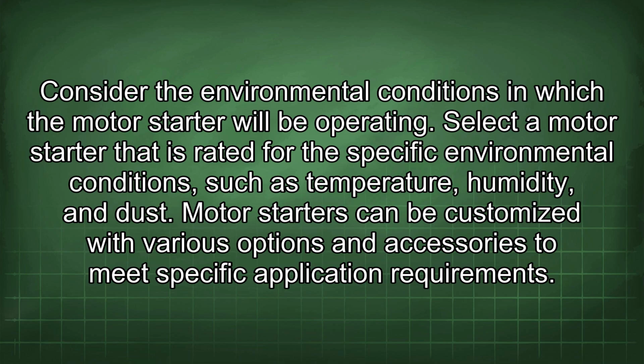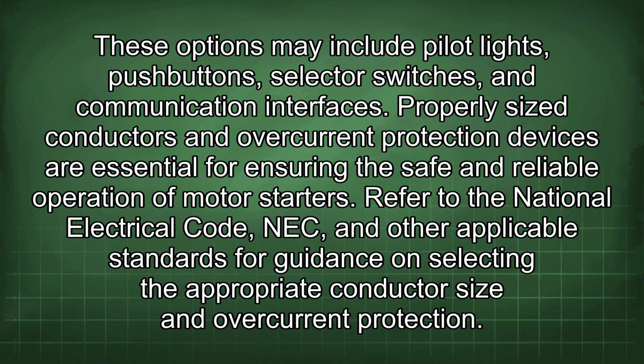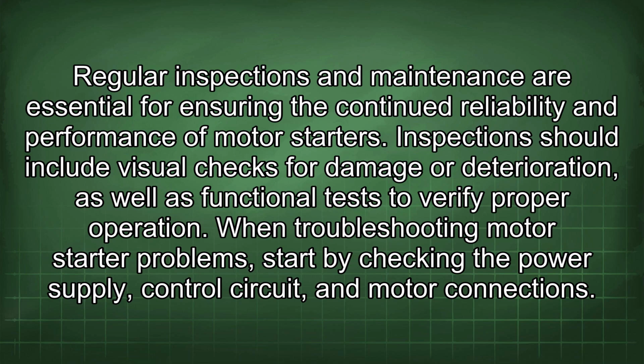Consider the environmental conditions in which the motor starter will be operating. Select a motor starter that is rated for the specific environmental conditions, such as temperature, humidity, and dust. Motor starters can be customized with various options and accessories to meet specific application requirements. These options may include pilot lights, push buttons, selector switches, and communication interfaces. Properly sized conductors and overcurrent protection devices are essential for ensuring the safe and reliable operation of motor starters. Refer to the National Electrical Code, NEC, and other applicable standards for guidance on selecting the appropriate conductor size and overcurrent protection. Regular inspections and maintenance are essential for ensuring the continued reliability and performance of motor starters.